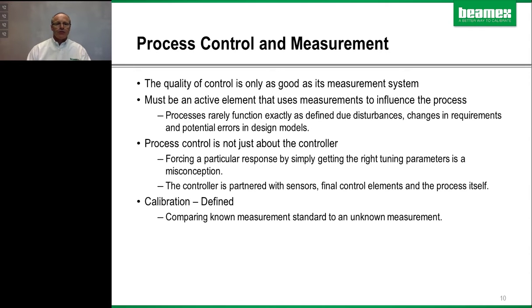It doesn't matter how exotic or how much you spend on your control system. If it's not getting good measurement data from the instrumentation, that is a very, very weak link. So these control instruments are responding to the process, and there are inherent changes that are primarily due to disturbances in the process, but also changing requirements, and hopefully not, but there could be some design flaws. The controller is the core of the system, but it is also dependent on, and partners with, the sensors that are measuring the process, the different control elements in the process, and also the process itself. So a competent control cannot really be achieved by simply putting all your resources into tuning the controller.